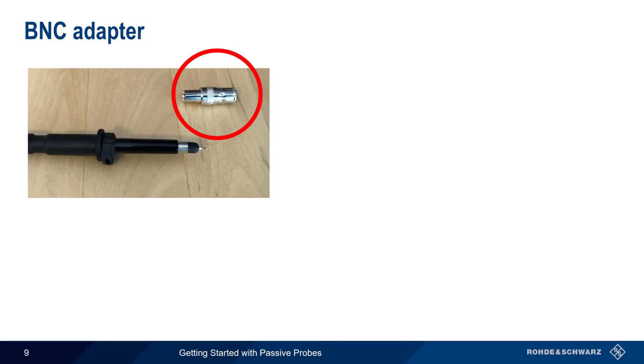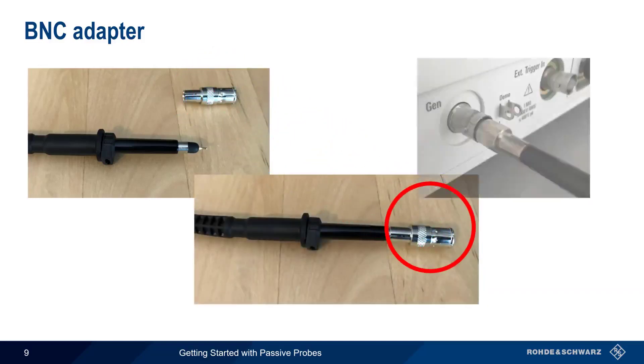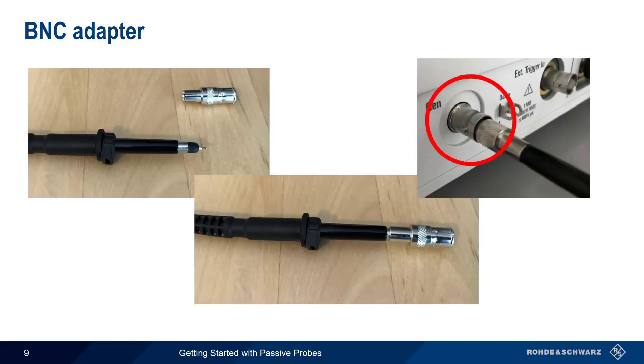In some cases, we want to connect our probe directly to a BNC connector, and this can be done using the BNC adapter. This adapter is slipped over the end of the probe tip, allowing the probe tip to be directly inserted into a BNC type connector.